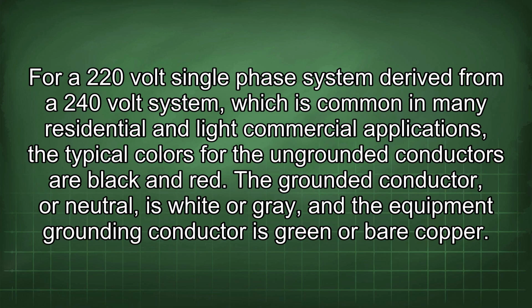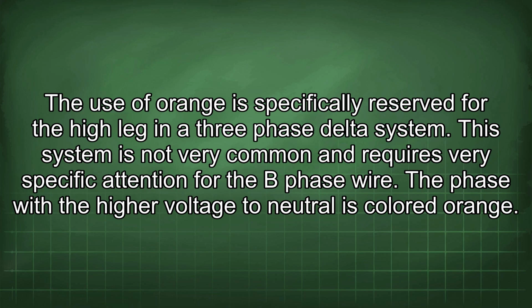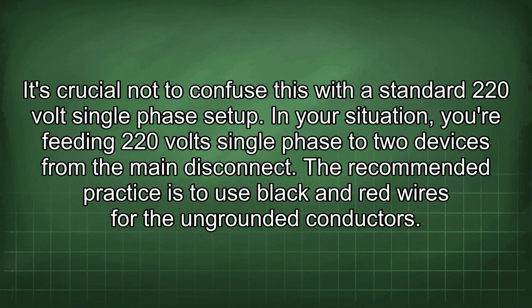For a 220-volt single-phase system derived from a 240-volt system, which is common in many residential and light commercial applications, the typical colors for the ungrounded conductors are black and red. The grounded conductor, or neutral, is white or gray, and the equipment grounding conductor is green or bare copper. The use of orange is specifically reserved for the high-leg in a three-phase delta system. This system is not very common and requires very specific attention for the B-phase wire. The phase with the higher voltage to neutral is colored orange. It's crucial not to confuse this with a standard 220-volt single-phase setup.